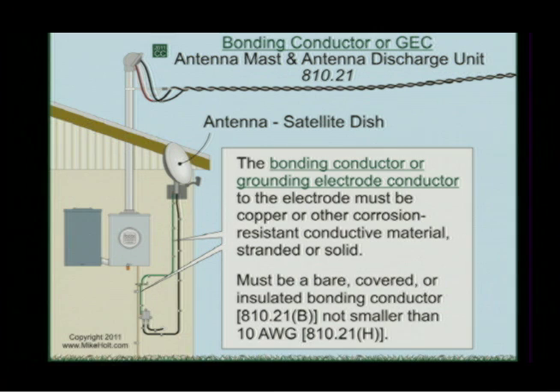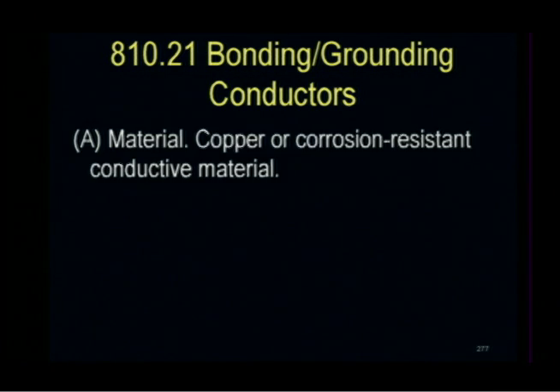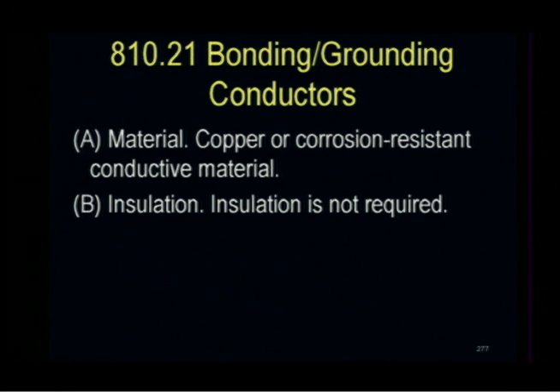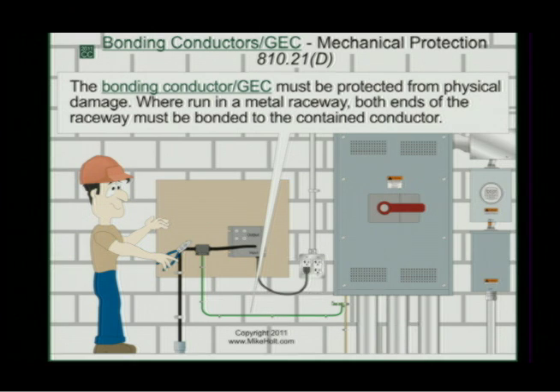What size wire is this? Not smaller than 10 gauge. So this is a 10-gauge wire for the bonding conductor. Article 810.21 — bonding and grounding electrode conductors must be copper or corrosion-resistant material. Insulation is not required. It must be securely fastened in place. The bonding conductor or grounding electrode conductor must be protected from physical damage. If it's running in metal raceway, you have to bond it at both ends.